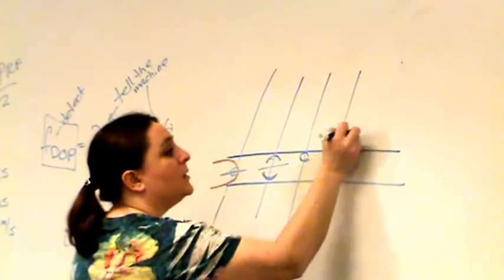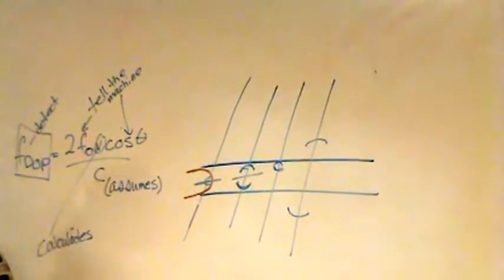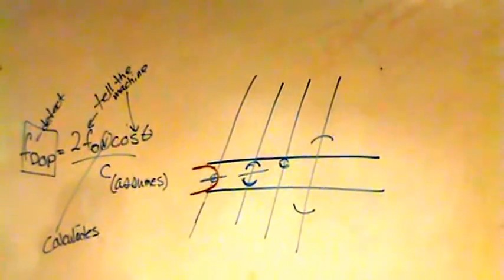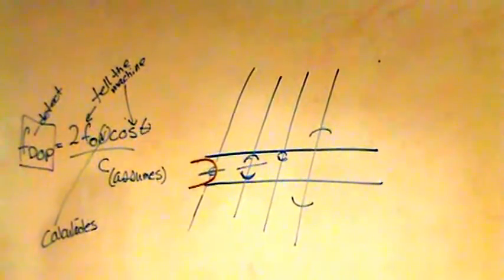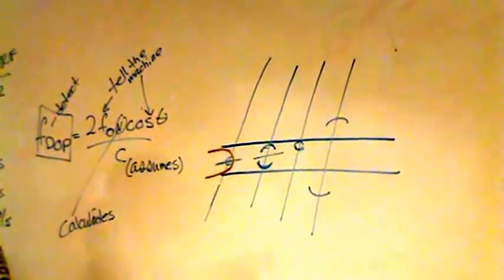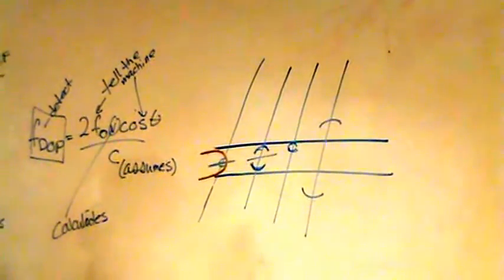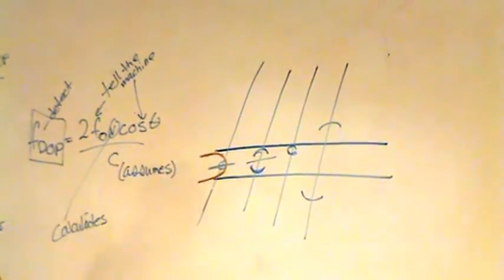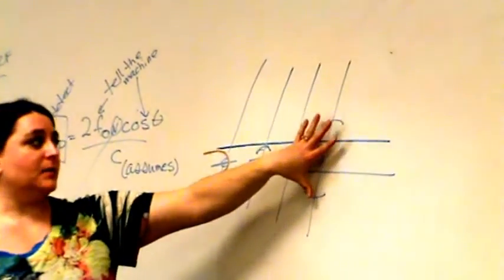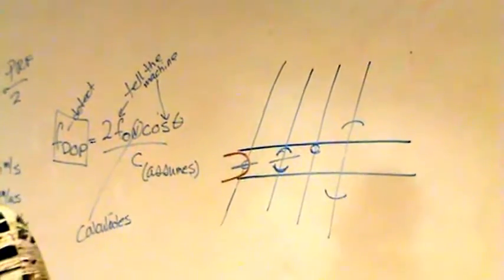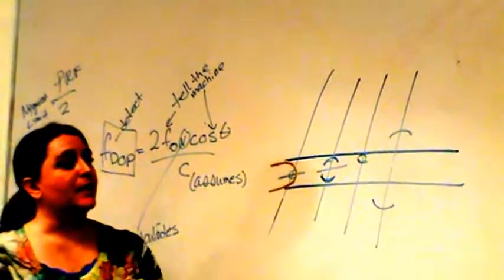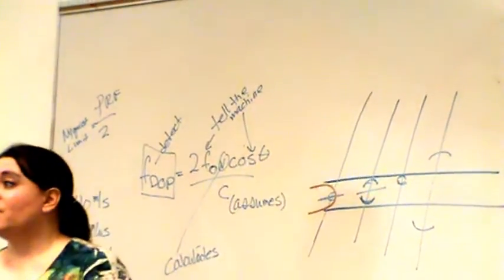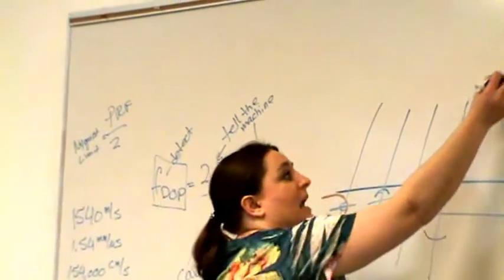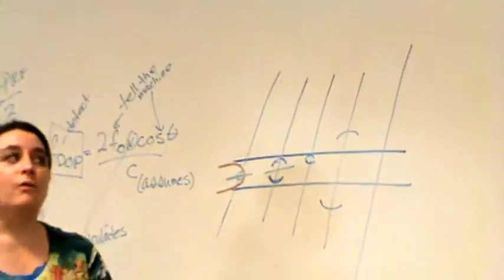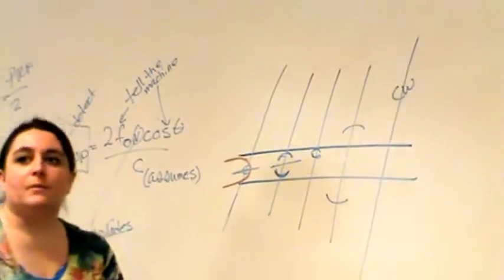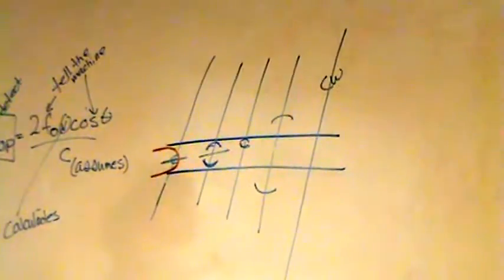If I have a sample volume so huge that it's outside of the vessel, not only am I going to get spectral broadening, but I'm probably even going to pick up more vessel wall thump. I'll have these low frequency, high amplitude thumps in my waveform, because I'm not only detecting flow inside the vessel, but I'm detecting the wall motion. That's going to increase my spectral broadening. If I'm using continuous wave, remember continuous wave listens, it doesn't have a sample volume, it listens across that entire range. So I'm definitely going to have spectral broadening when I'm using CW.